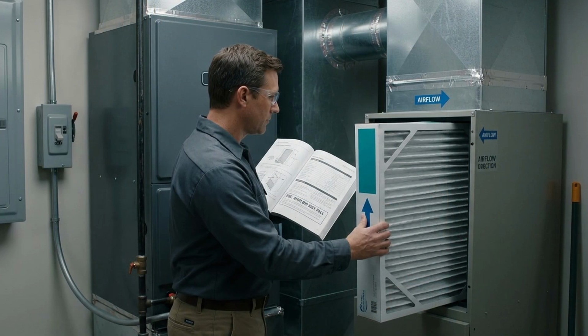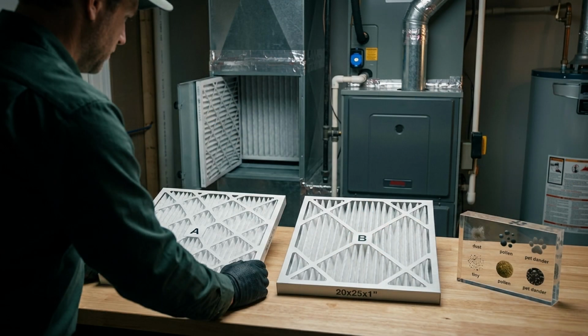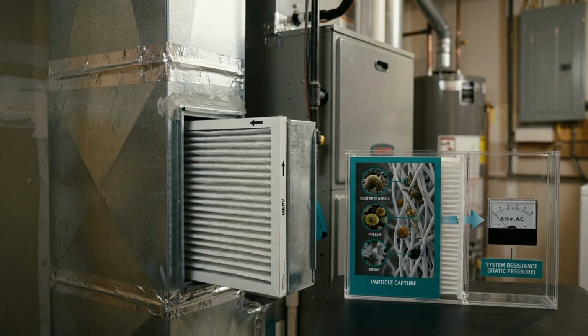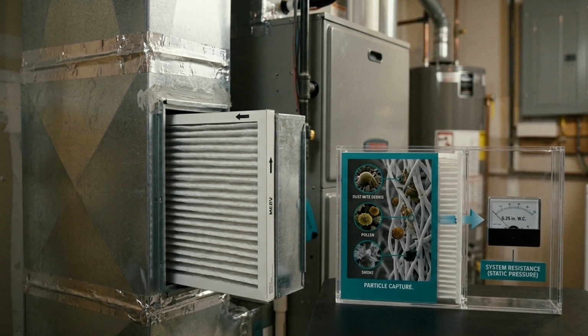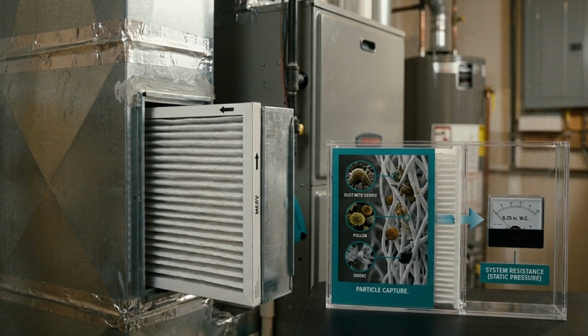The manufacturer's performance table may show different resistance at the airflow your equipment needs. Now compare the same deep filter when new and after it has collected a substantial dust load. Its rating has not changed, but its operating resistance may have. This is why a photo of the label or a MERV number by itself cannot settle the airflow question.